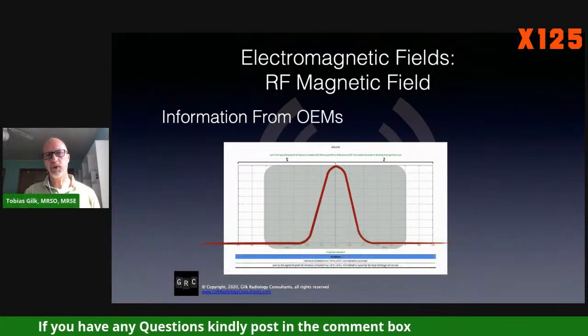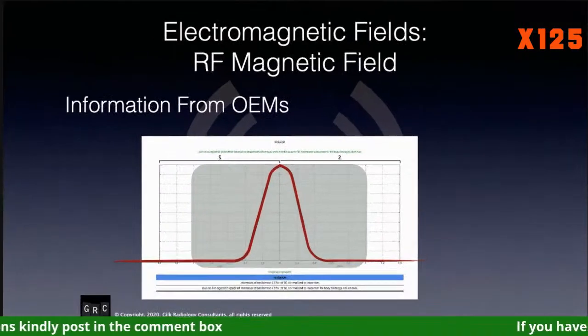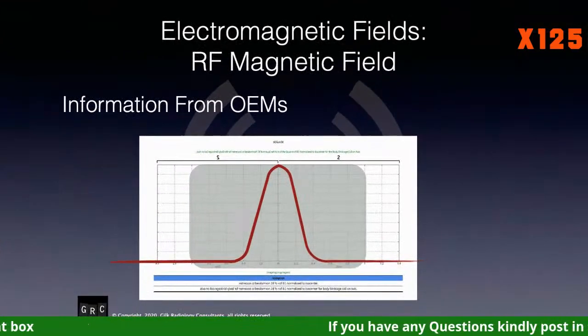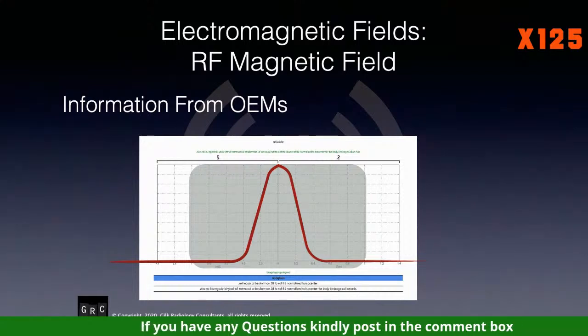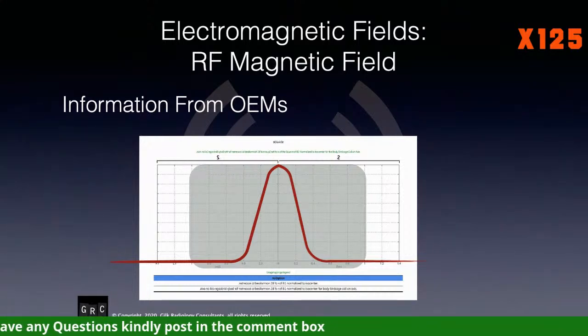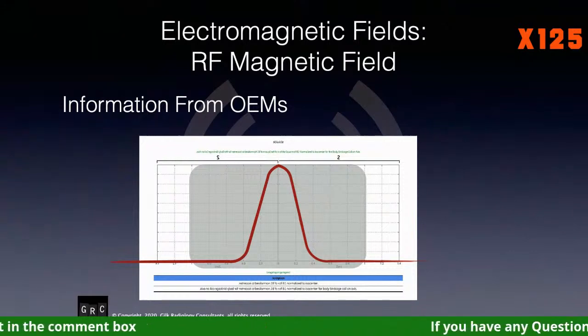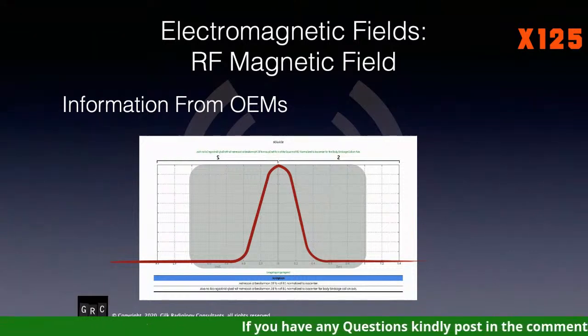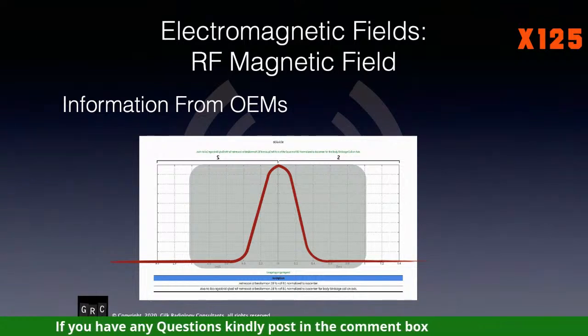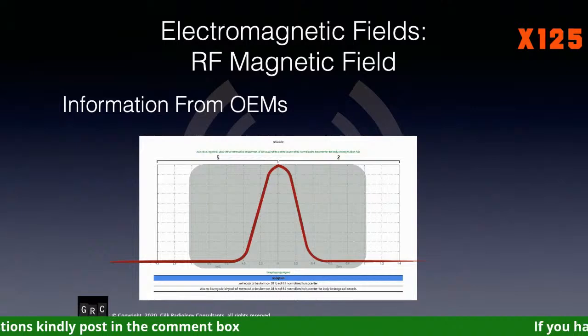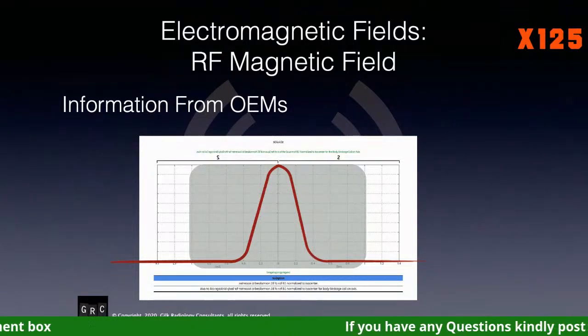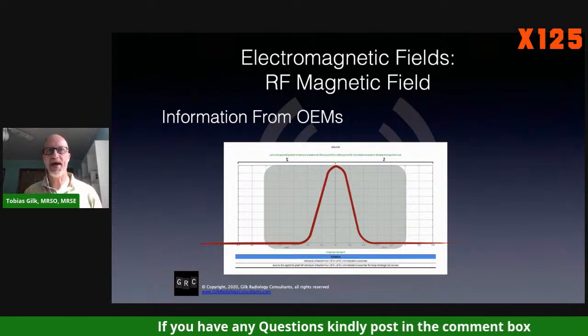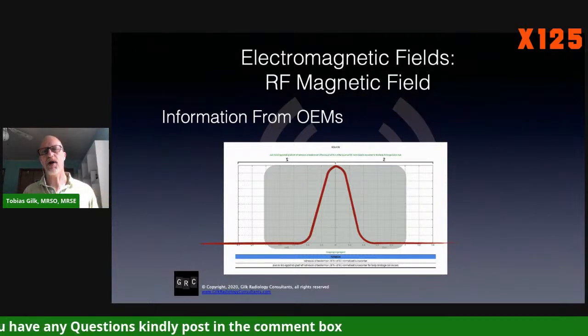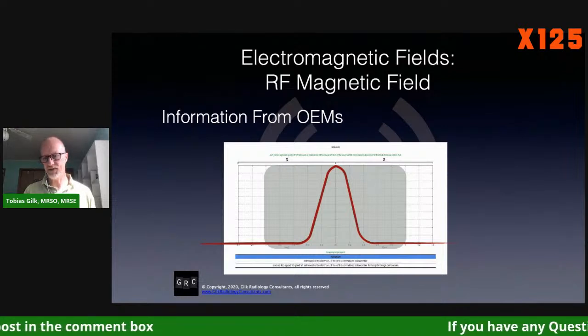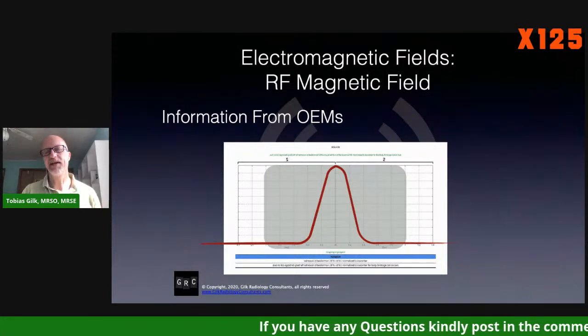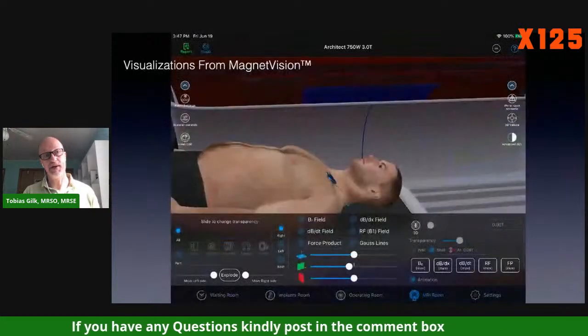Now this curve is showing proportional energy, and dead center in isocenter, it's showing the proportion being 1, maximum. And then as you move superior or inferior along the z-axis, you can see that the RF energy drops off dramatically. So what does this diagram tell us? Well, this diagram tells us that radio frequency energy is maximum at isocenter, and that it drops precipitously as you move away from isocenter. Unfortunately, that's not the least bit accurate.